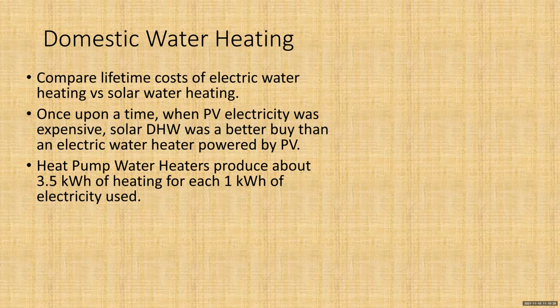But now it's possible to buy a heat pump water heater. What they do is suck heat out of the surrounding air, which means they act as an air conditioner, and they put that heat into the water with a coefficient of performance of about 3.5. So for every kilowatt hour of electricity you expend, you're getting 3.5 kilowatt hours of heating. In other words, the cost of heating water with electricity has been reduced by a factor of 3.5.